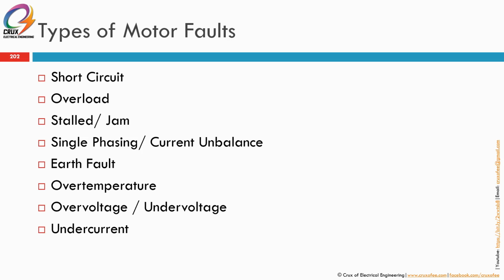So we have the typical types of motor faults you can experience: short circuit, overload, stall or jam rotor, single phasing, current unbalance, earth fault, over temperature, over voltage and under voltage, as well as undercurrent. Undercurrent is not really protection for the motor, but mainly for the load. For example, if an impeller is driving a compressor or a pump and the impeller is lost or broken, it will show as underloaded, under current.